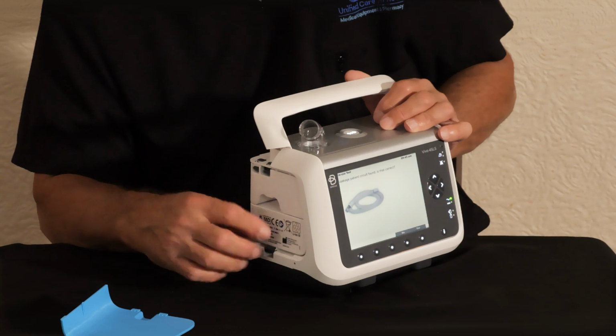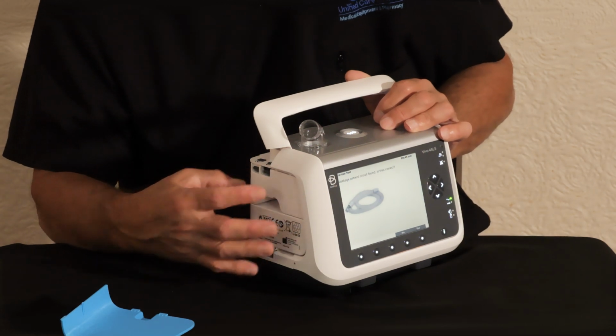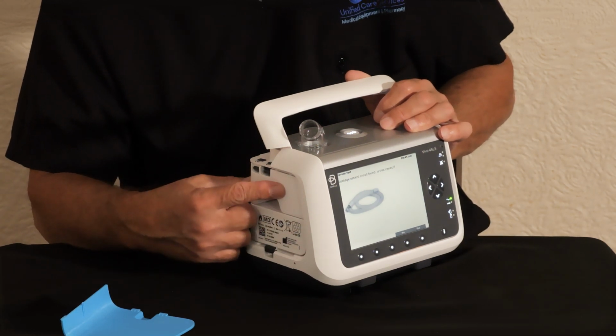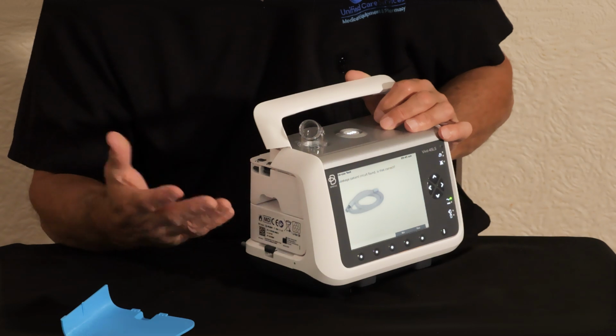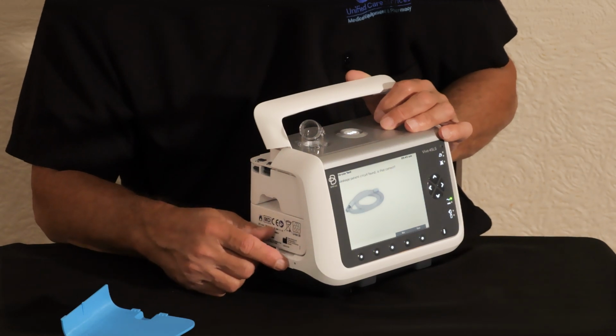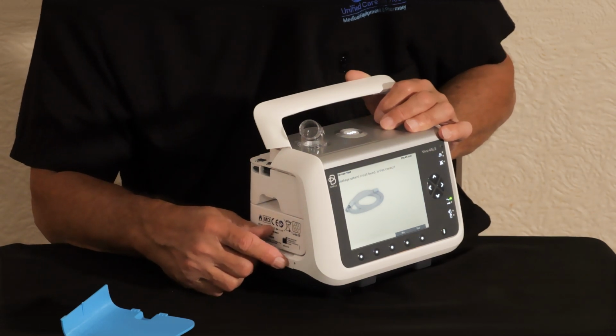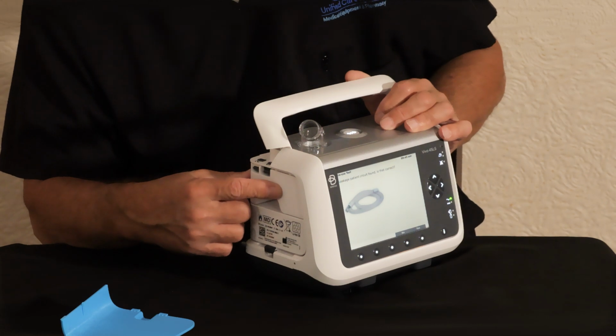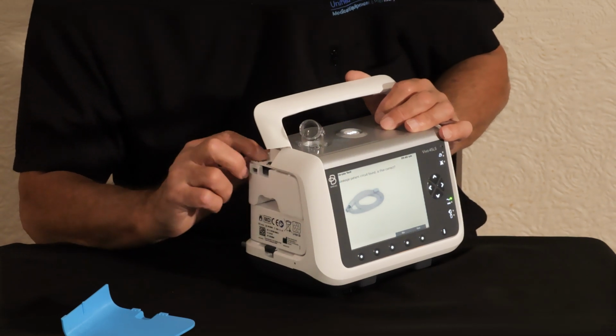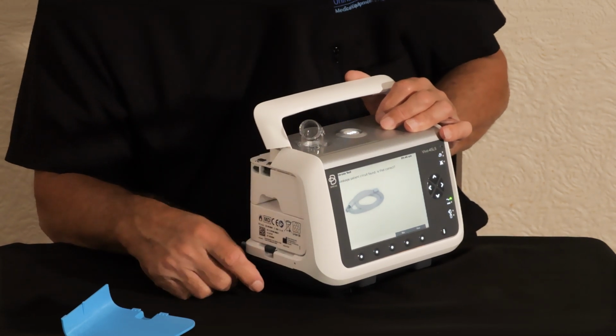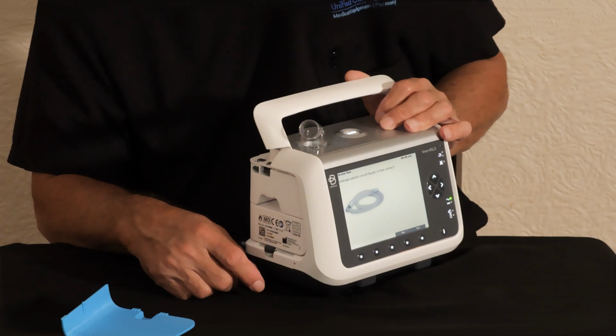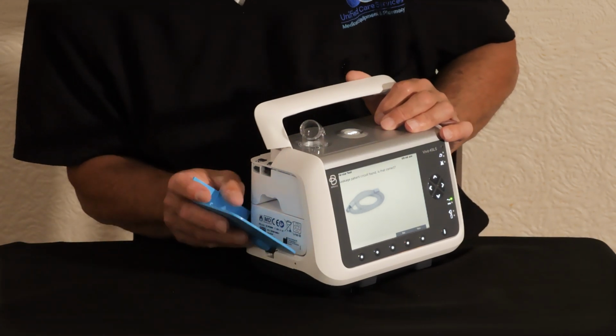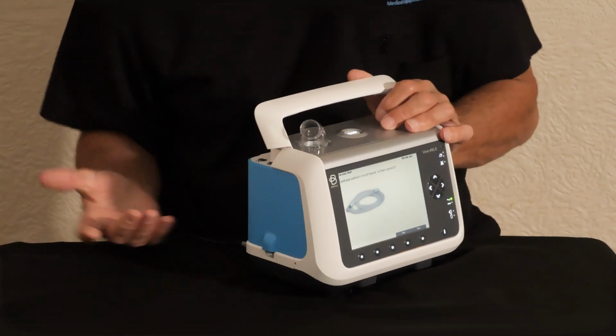Now, above the battery sits what's called the humidifier bypass, and this has to be all the way inside to the point where you hear it click. If it's not pressed all the way inside, you're going to get an alarm when it's actually in use, and the alarm will say humidifier bypass. It's always going to be that this has come loose, and all you have to do is push it in to silence that alarm. To put the door back in, you simply present it and get it to click.